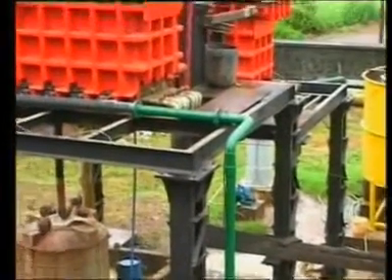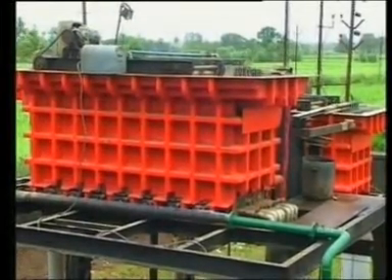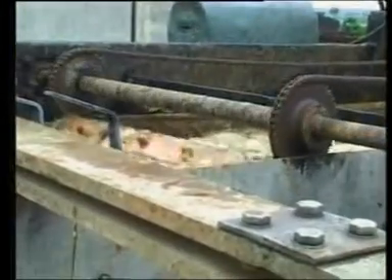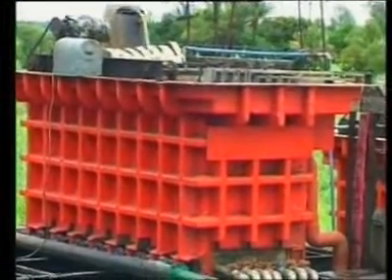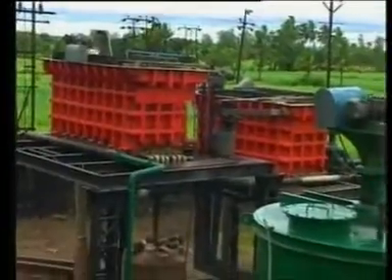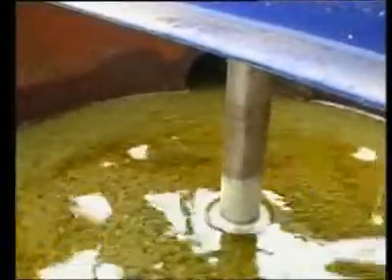Then the effluent is pumped into the advanced oxidation process chambers. In these chambers, suspended solids are brought up on the surface through flotation, where these are removed by a custom-made skimmer, while the dissolved solids are removed with the help of high oxidation potential hydroxyl radicals. These radicals are continuously generated in the chambers and oxidize and destabilize the colloidal matter in the effluent. This enables breaking the notorious black color of the effluent, converting it into a mixture of precipitative solids and liquid with a light and bright yellow color.